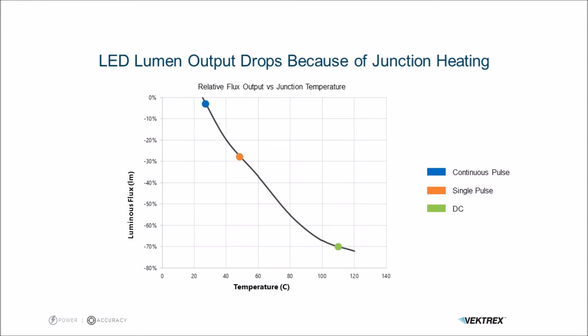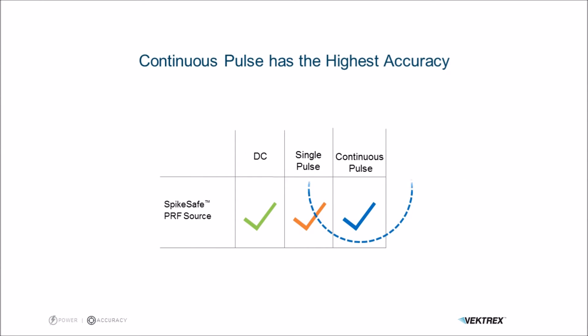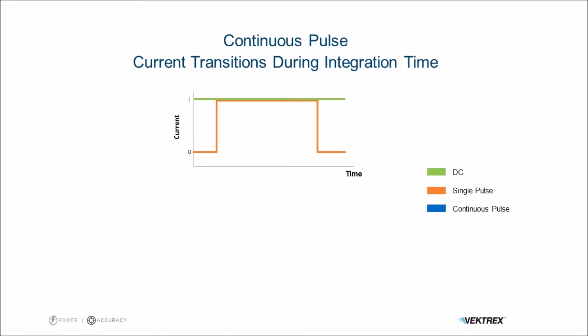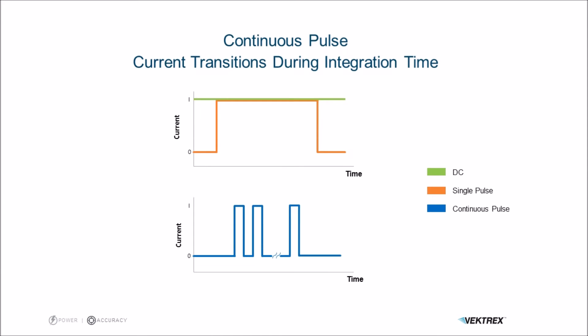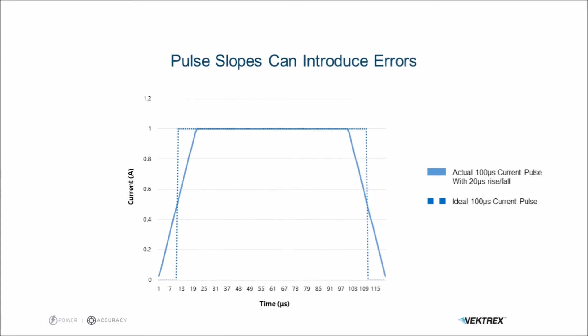So continuous pulse is obviously the best or most accurate measurement. But what do we need to know about continuous pulse? Continuous pulse is a little different from single pulse and DC in that the current actually transitions up and down during the spectrometer integration time. The integration time incorporates one or a series of pulses rather than having the current on before the spectrometer starts. This means that the slope sides — the rise and fall — are part of the measurement.